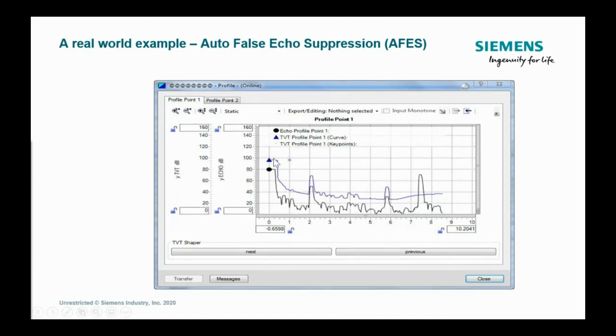So what it did is the process went and it mapped around the bell end, it mapped around the other bell end, and then how many valid echoes do I have left? One. Problem solved. Okay. Now, usually somebody really smart in the room says, hey, but wait a sec, Mark. As this thing fills up, this echo is going to migrate to the left. Yep. So when you're down at 10 feet, it's going to be here, just a little bit more than 3 meters. Well, what happens when this echo gets inside of this zone that it's mapped out?